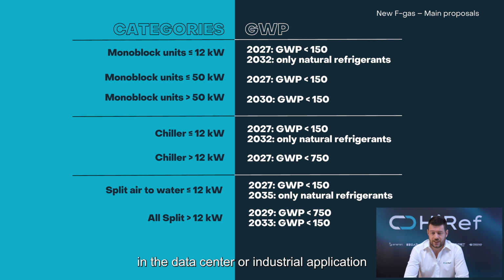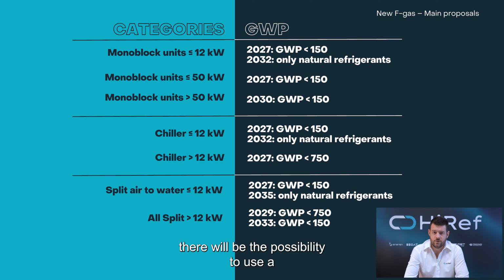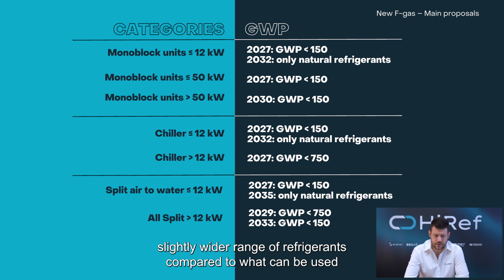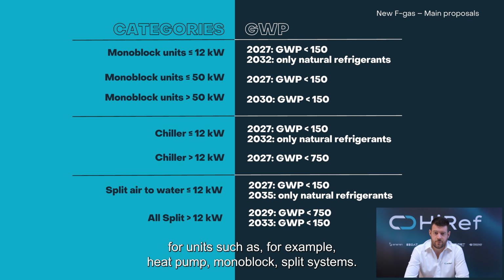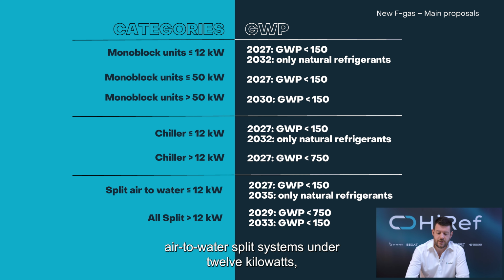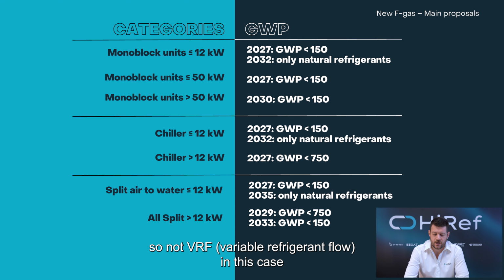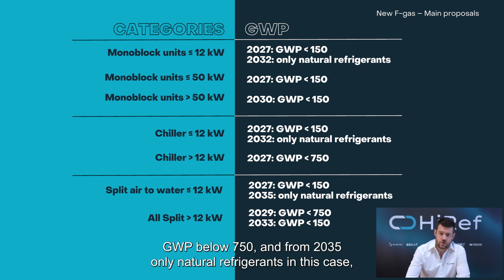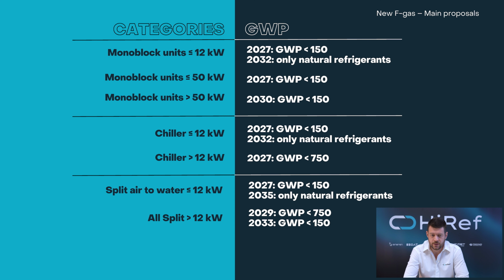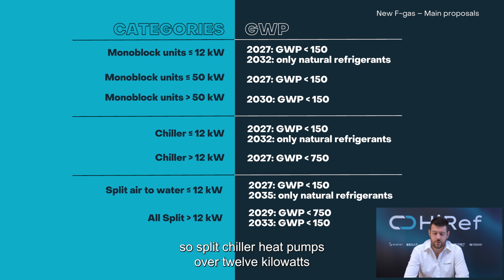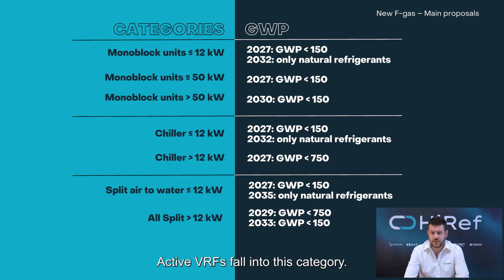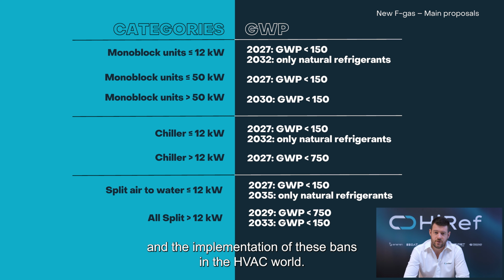So, in data center or industrial applications, there will be the possibility to use a slightly wider range of refrigerants compared to what can be used for units such as heat pumps, monoblock or split systems. For split systems we have two distinctions: air-to-water split systems under 12 kW, so no VRF, variable refrigerant flow, in this case still with a 2027 deadline, GWP below 150, and from 2035 only natural refrigerants will be available, whereas for the rest of the split systems, so split chillers, heat pumps over 12 kW, active VRF, fall into this category. The two dates are 2029 with GWP below 750, and from 2033 we again see GWP below 150. So this slide summarizes an overview of the bans and their implementation in the HVAC world.